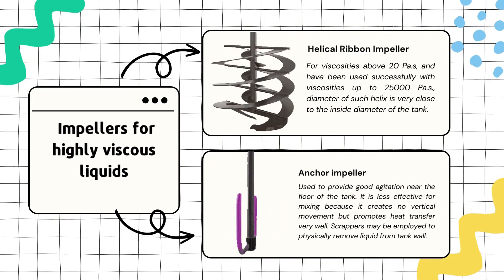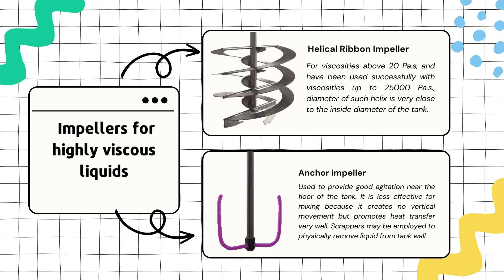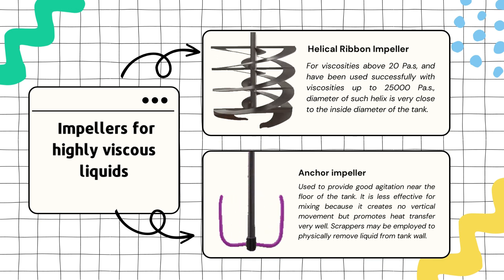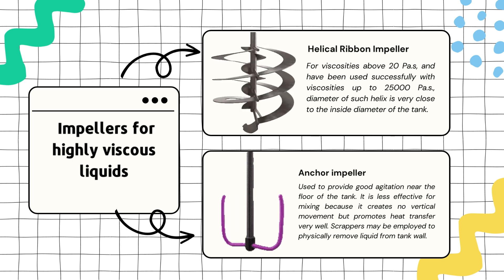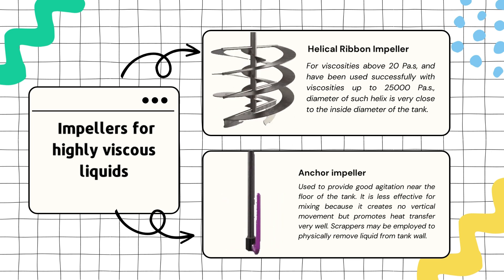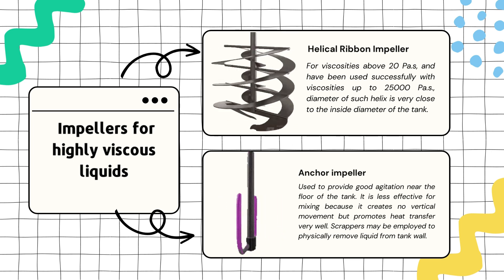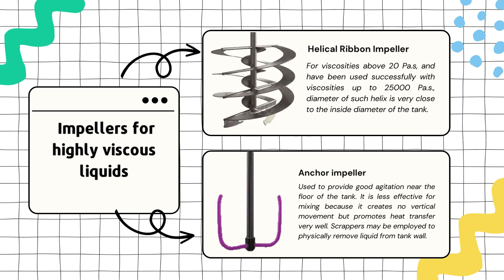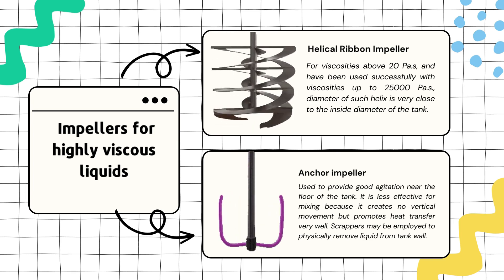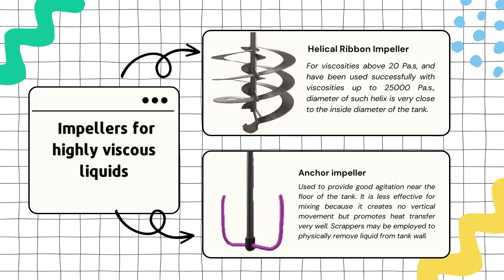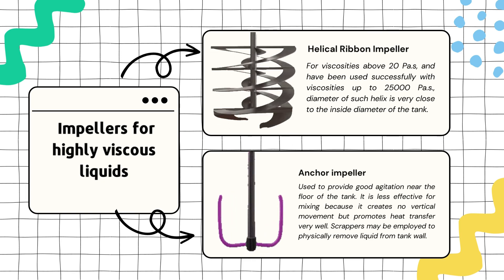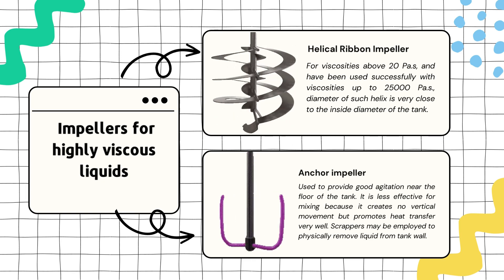When dealing with high viscous liquids, specific impellers are employed. The first is the helical ribbon impeller. This type of impeller is used for viscosities above 20 pascal seconds and has even been used successfully with viscosities as high as 25,000 pascal seconds. The diameter of this helix closely matches the inner diameter of the tank.